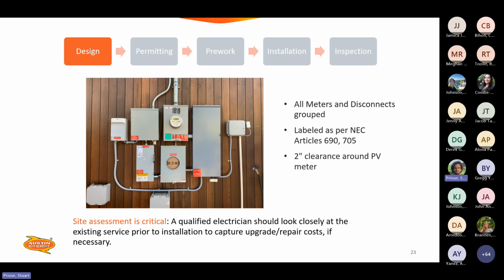And here's an example of an equipment wall that is designed well. You've got your meters grouped and your disconnects grouped. So if there was an emergency at all, meters could be pulled, and within one step, emergency personnel could disconnect the main service and the PV service without having to relocate. And also it's got all labels as per NEC 690 and 705. It's important too that an electrician takes a close look at these services before installation, because you don't want to get caught in a situation where there are expensive upgrades that were not accounted for in the beginning of the process.